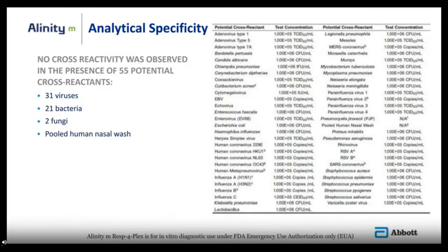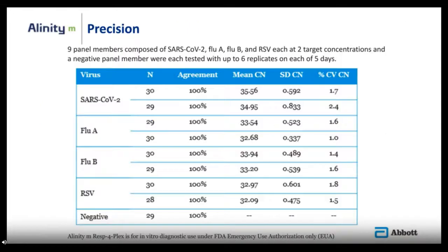In the analytical specificity study, 55 potential cross-reactants were tested, including 31 viruses, 21 bacteria, 2 fungi, and a pooled human nasal wash. No cross-reactivity was observed with any of these potential cross-reactants. For precision, nine panel members — two target levels each for SARS-CoV-2, flu A, flu B, and RSV, plus a negative member — were tested across up to 30 replicates over five days. 100% agreement was observed compared to expected results, and excellent precision was demonstrated by evaluating SD and percent CV of PCR cycle numbers.